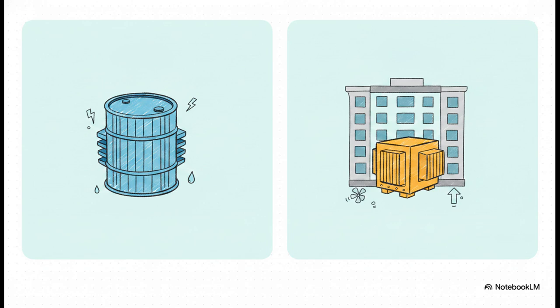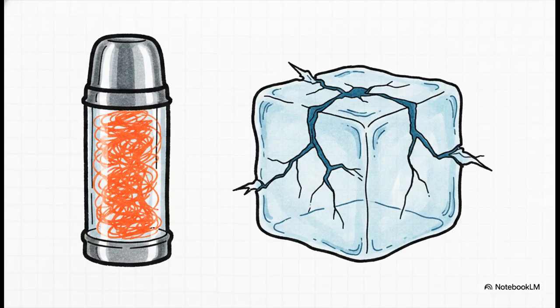On the flip side, we have dry-type resin-encapsulated transformers. These use solid epoxy resin and just regular ambient air to cool down. They're definitely bulkier, but they are fire-safe, which makes them the go-to for indoor setups. Also, oil units can go about 15 years between major samples, while dry types usually need visual and thermal scans every single quarter.